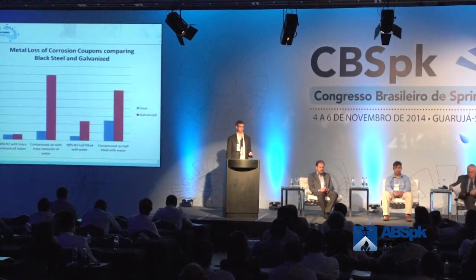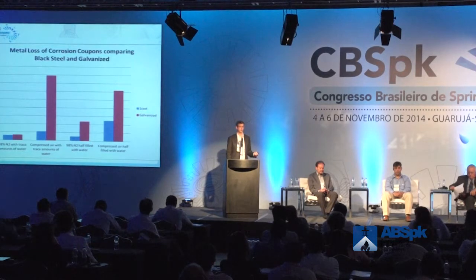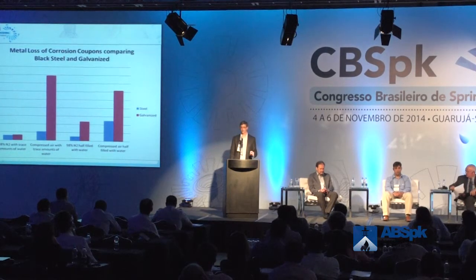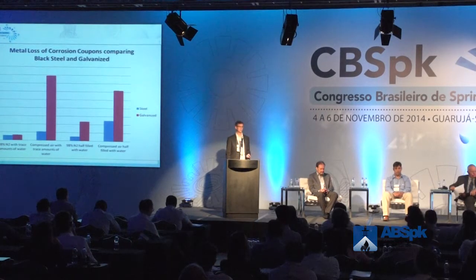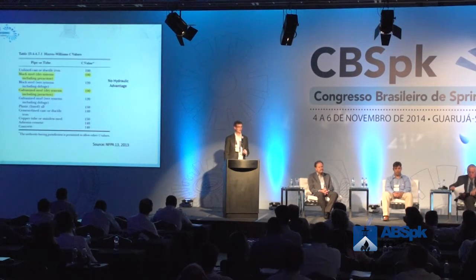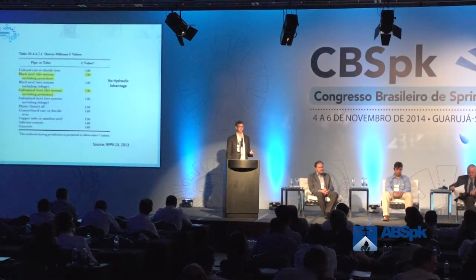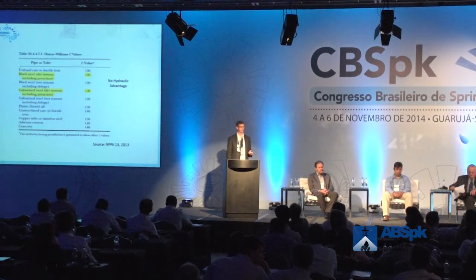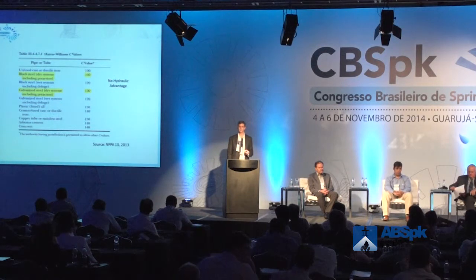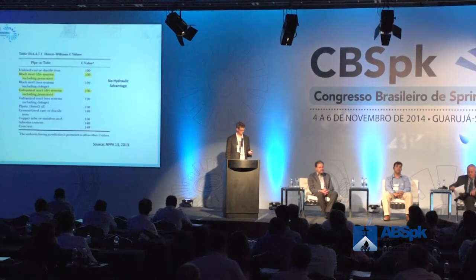We also found something very interesting. The old adage was that using galvanized on dry and preaction systems would slow down corrosion. But what we've actually established through testing is that it doesn't really help. In fact, in some cases, using galvanized is worse. And that's actually made a change in the NFPA itself. What we see now is that the C factor for galvanized pipe in dry and preaction systems is now the same as a black steel system. So you're no longer getting a hydraulic advantage by using galvanized.